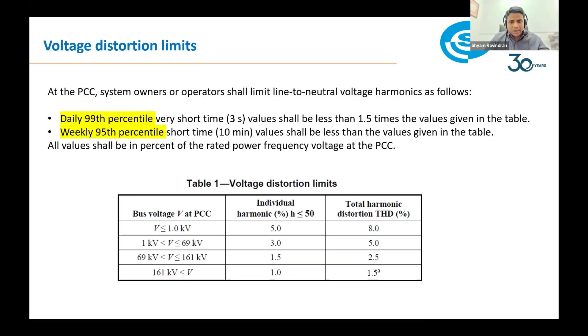Now, I mentioned in the beginning of my presentation about Class A and Class S analysis. This is very important because all these reports and definitions shall be done, not only by us, but by any company today that has a 61000-4-30 edition 3 certificate with IEEE 519 2022 implemented in their products. You will be able to do this after the recording, taking out the data with just a few clicks. This reporting shall not always need to be done by a PQ expert. In many instances, even people who do not know the standard shall be able to take out the report and work out the limits, because the report is able to classify it as events. So when you take out the reports, how many times the limits are exceeded will be clearly shown in the IEEE 519 reports.